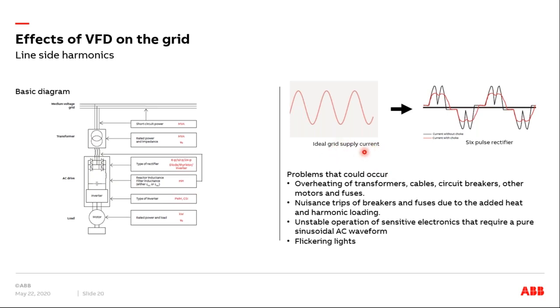that's going in, but a rectifier is not such a good conversion device. Like a diode bridge rectifier is not such a good conversion device, I would say. So if you take a 6-pulse rectifier, your purely sinusoidal waveform will look more like this black curve, with two different teeth, like a sawtooth kind of waveform. So it has a lot of harmonics, and it's in the range of 90% harmonics.